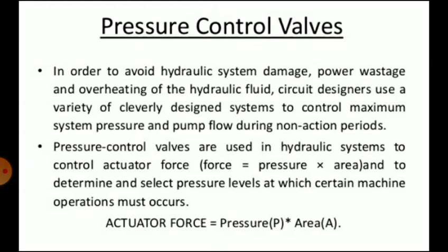Pressure control valves are used in hydraulic systems to control actuator force. Force is equal to pressure times area, and they are used to determine and select the pressure level at which certain machine operations must occur.